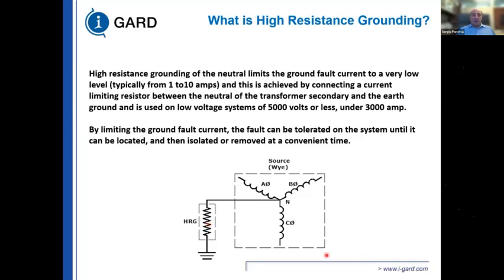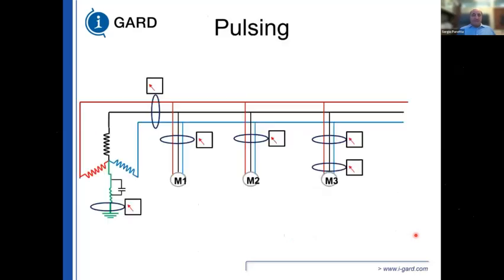Remember, we said earlier that all faults have to return back to their source. And if there's an impedance in the source, we limit the fault current. So that same fault we had at 40,000 amps is reduced to 5 amps simply by putting a 55 ohm resistor in here. The one thing you do sacrifice is that you do not have a distributed neutral. The best part of a high resistance grounded system is the ability to locate where the fault is.